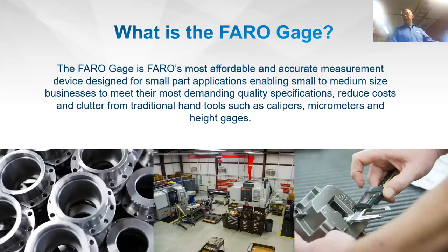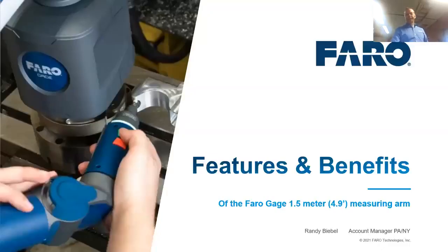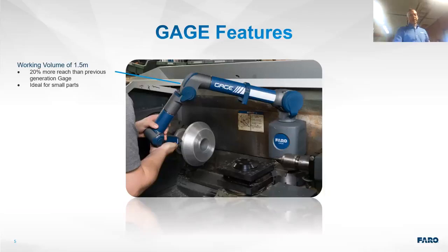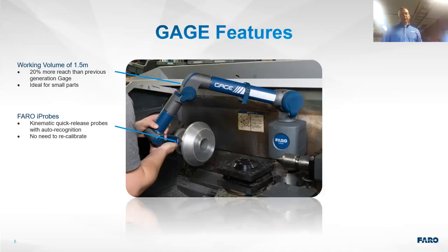The Faro Gage is a 1.5-meter or 4.9-foot measuring device. Its working volume is 20% more than previous Faro Gages, making it ideal for smaller parts. Faro now has i-Probes — kinematic release, quick-change probes — so you don't need to recalibrate when switching from a small, sometimes fragile probe to a larger probe for other types of dimensions.